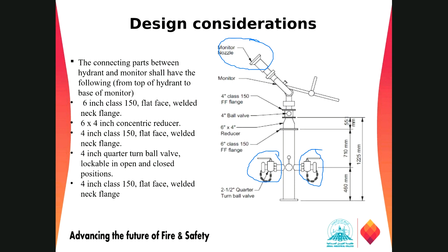The connecting parts between hydrant and monitor shall have the following equipment, from the top of the hydrant to the base of the monitor. We have a 6-inch class 150 welded neck flange. This is the first one. Then we have a reducer of 6-inch by 4-inch. After that, we have a 4-inch ball valve to close the monitor in most cases, and just open it when we require to get water. Then we have a 4-inch flange, and then it is connected to our monitor nozzle.